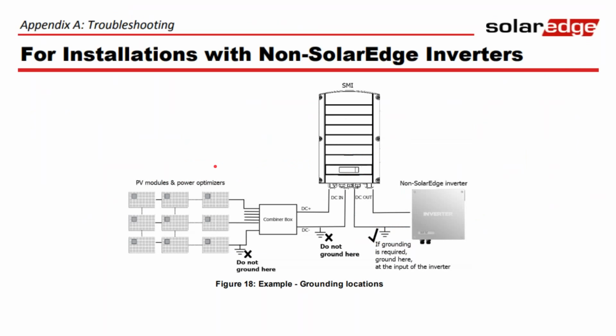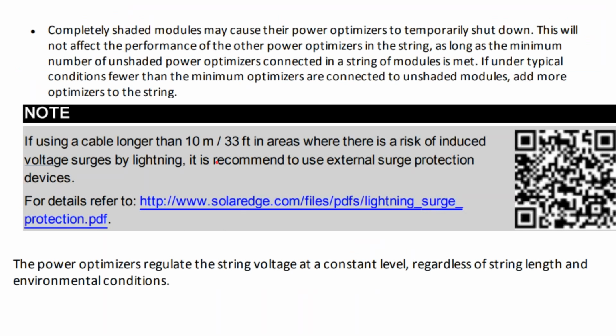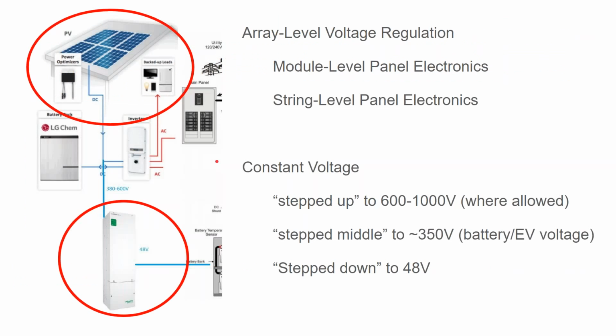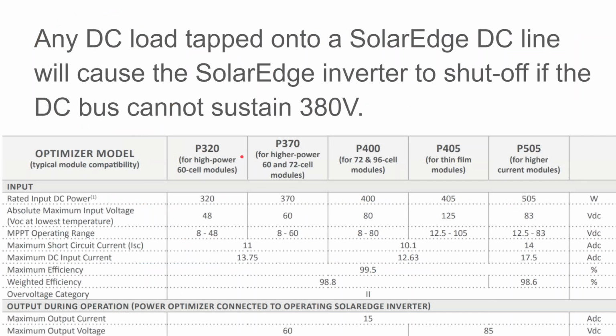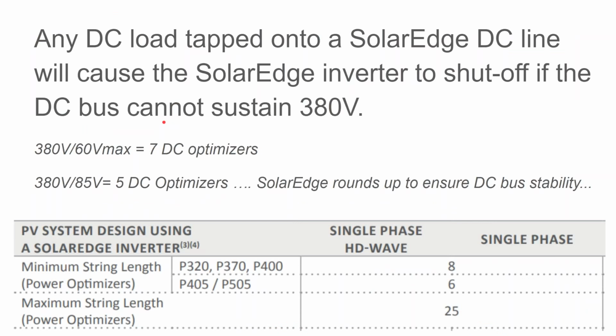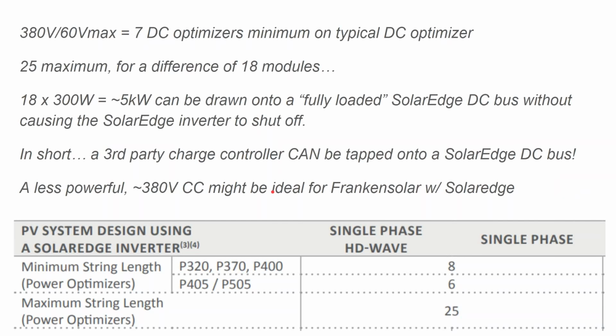So the rest of these slides go through how Solar Edge says you're not allowed to do this stuff, you're going to void the warranty. But when you read the spec sheets, you realize there's a minimum number of panels needed to turn the system on, and a maximum number before you're overpowering the inverter. The range of power in between is how much power you can draw off the high voltage DC bus without disrupting the inverter protocol.